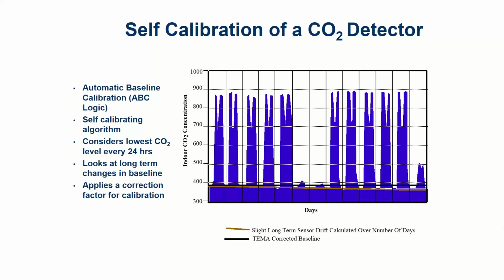So what ends up happening, if your building goes unoccupied at least 4 hours per week, total per week, not per day, per week, then we can do the automatic calibration. If you never go unoccupied, then we're going to have to calibrate a lot, right?